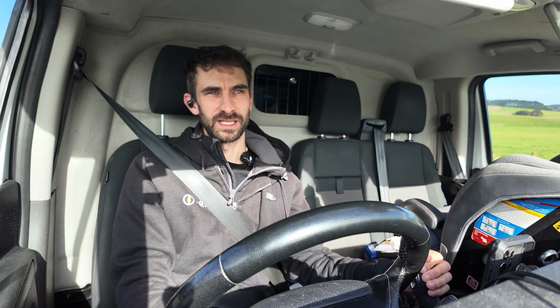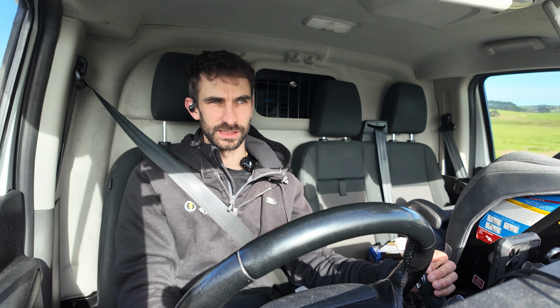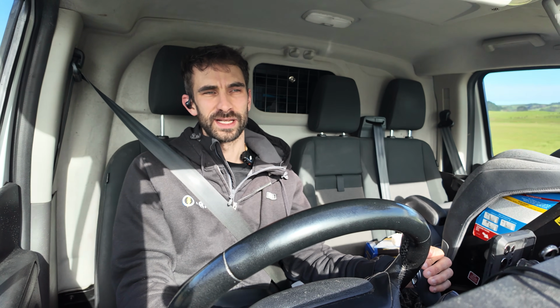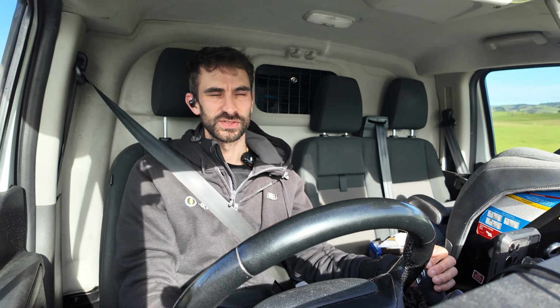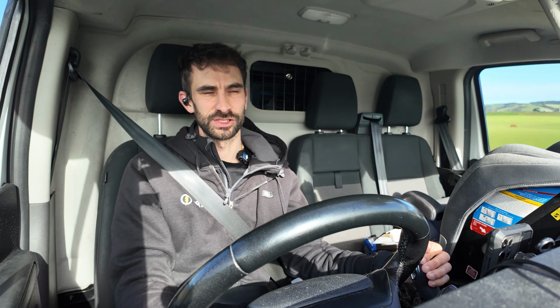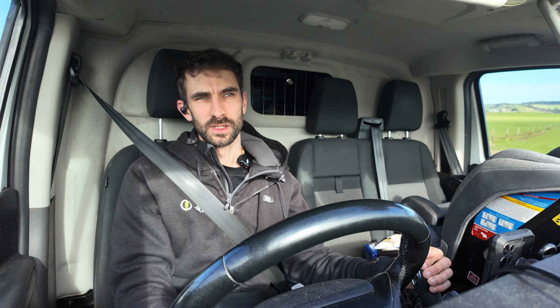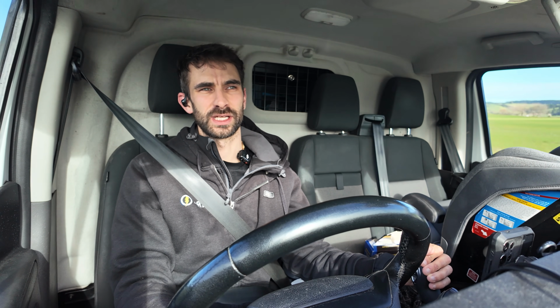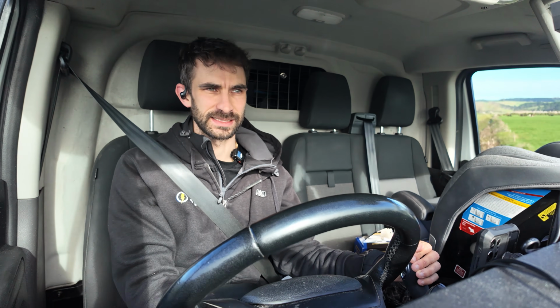And 500 milliamps isn't really enough to protect a person, but what it's doing is protecting against a fault. So if that fault occurs, it should trip because of the fault, not because of a person getting an electric shock. And then we have sub-circuit RCDs to protect against a person getting a shock.